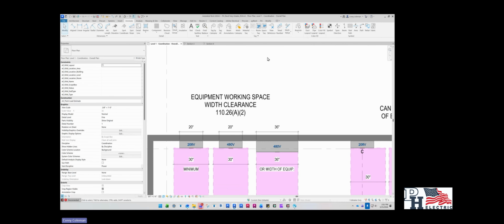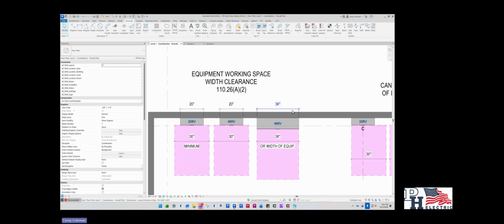So first, we're going to start with all the NEC required clearances. And the first one we're going to start with is equipment working space, which is the width clearance. When you get a panel or any piece of equipment, the minimum width that piece of equipment needs for its working space width-wise is 30 inches. As you can see, for a smaller branch panel, it's going to be a little bit larger than the panel itself. But when you get a larger distribution panel or larger equipment such as ATSs or switchgear, it's going to be the width of the equipment at minimum. So as you can see, this panel is 36 inches. That width of the working space needs to be the same width of the panel itself or the equipment.